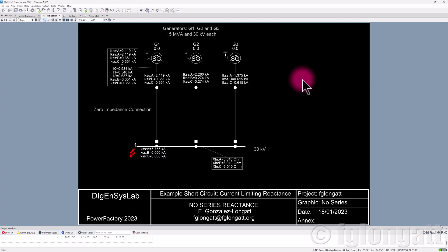During a fault condition, a circuit breaker that is over its rating will not be able to interrupt the short circuit. The energy dissipated in the process of trying to interrupt that short circuit current can create a very dangerous situation — for instance, the explosion of that circuit breaker. We need to do something to control the short circuit levels.